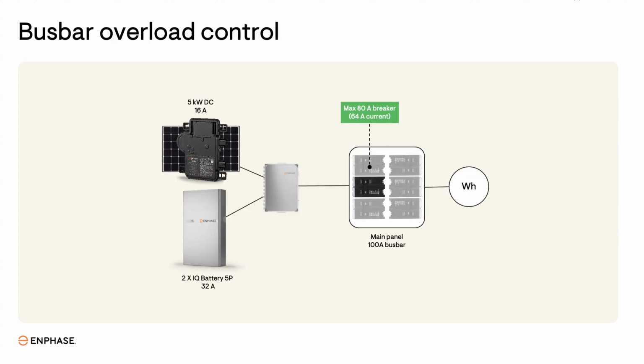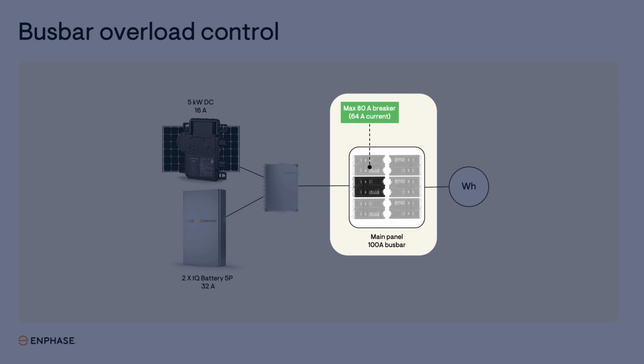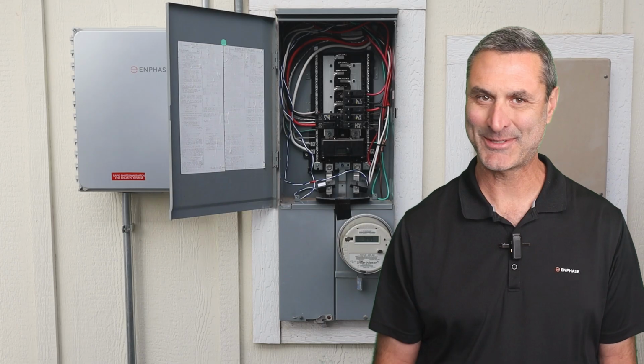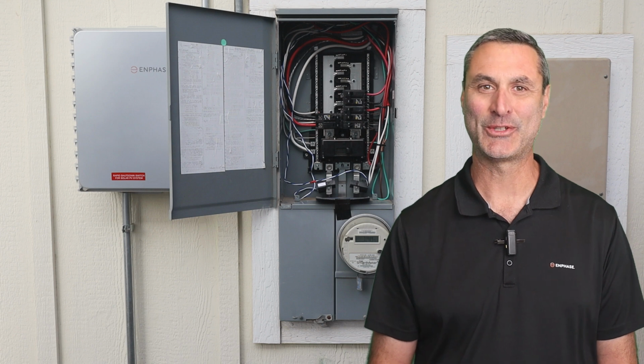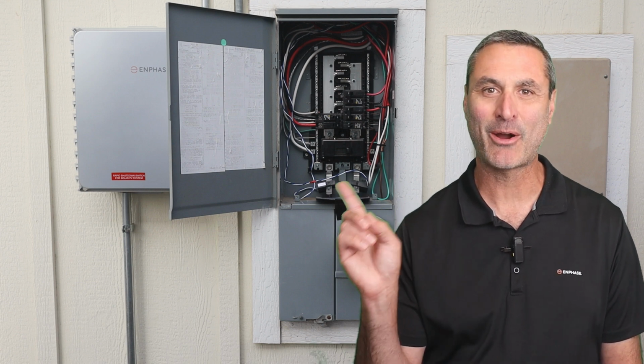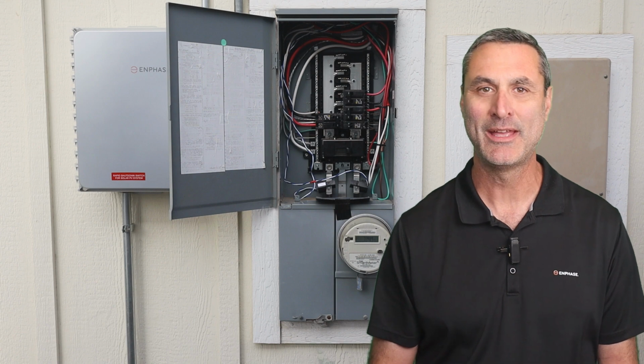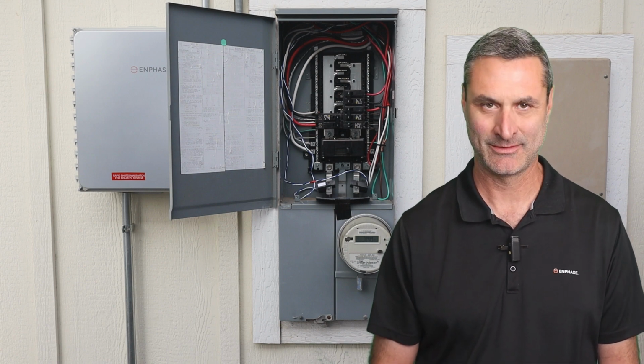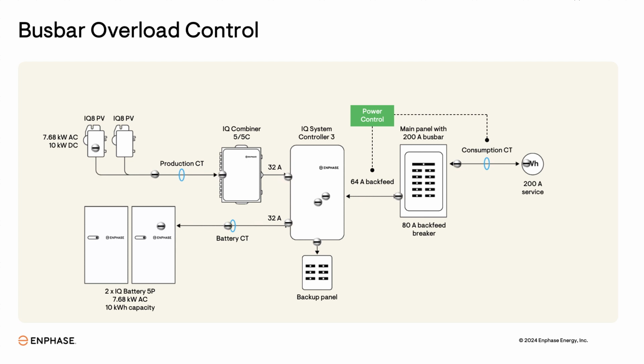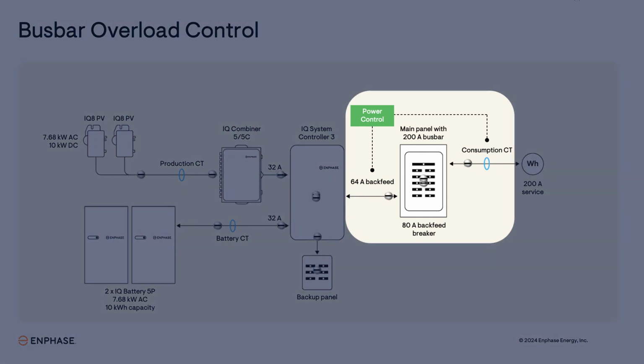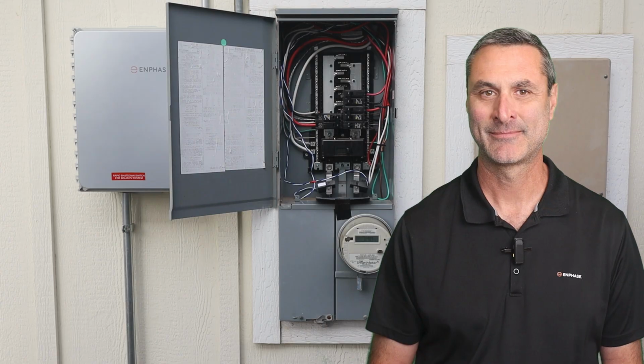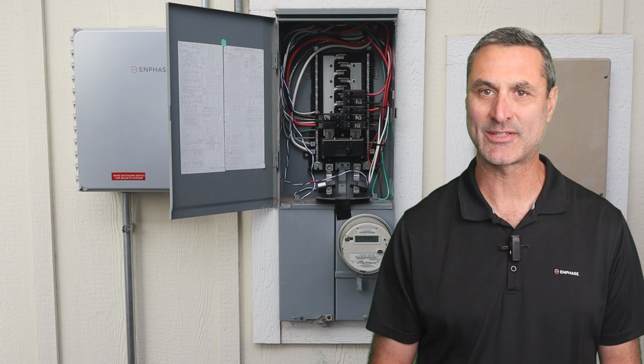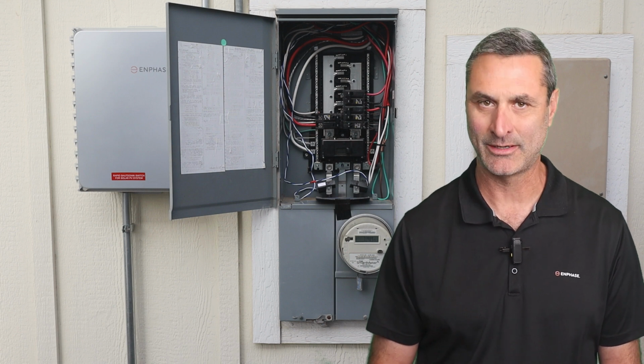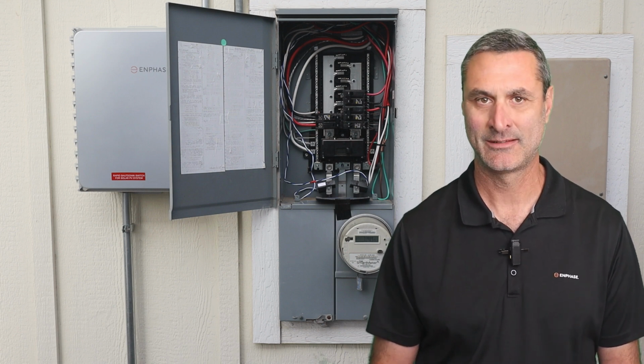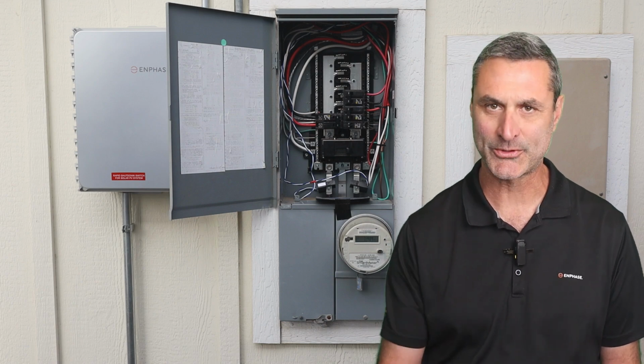Now, with Busbar Overload Control, the backfeed breaker limit is increased from 20 amps all the way up to 80 amps. How is this possible? Busbar Overload Control is all about ensuring that the bus bar, the metal bar inside the main panel that distributes power to the home, never gets overloaded and becomes a safety hazard. Think of the bus bar like a busy intersection full of cars, and power control is like a super smart traffic cop making sure everyone is safe and that traffic keeps flowing smoothly. This intelligent approach allows the solar and battery system to always deliver their maximum amount of power, which has two real-world benefits. First, homeowners will self-consume more solar energy.